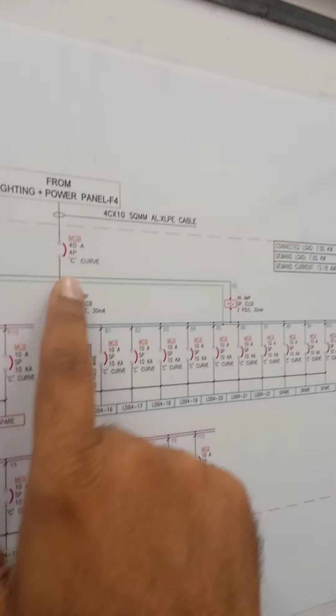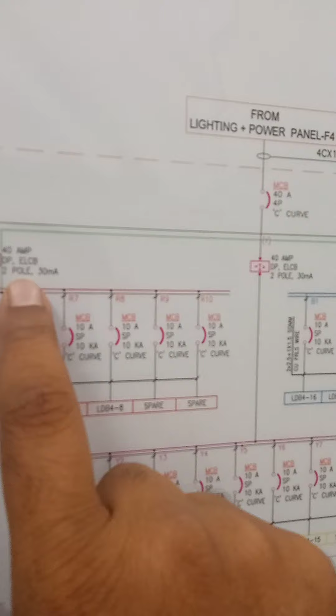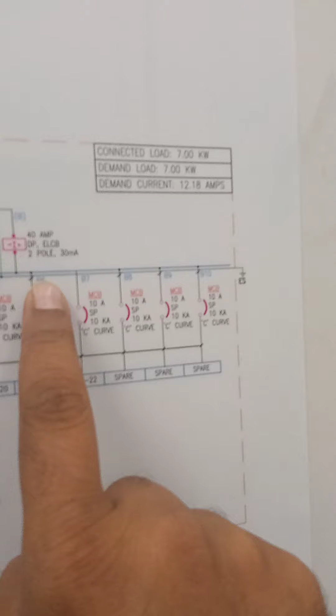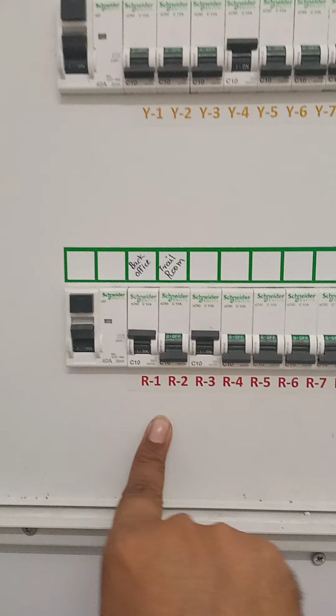Now from this it goes to red R phase, 40 amp ELCB. 40 amp ELCB yellow, 40 amp ELCB blue - 3 phases, and all phases have 10 MCBs. After the ELCB it goes to the MCB - first the 4 pole MCB, and this is the single pole MCB. Okay, all is the same.